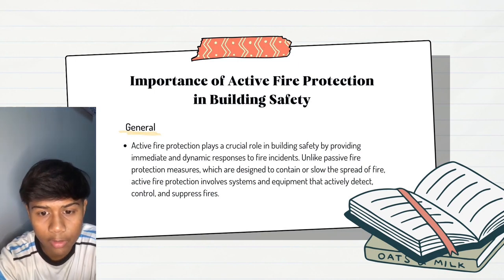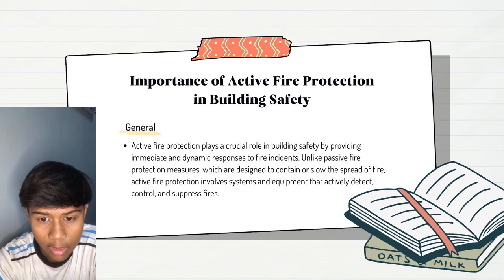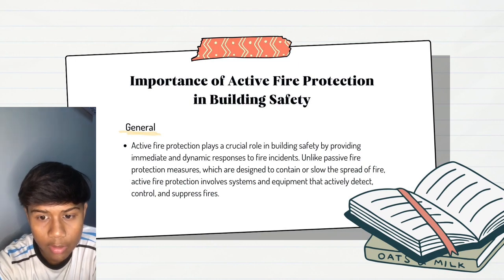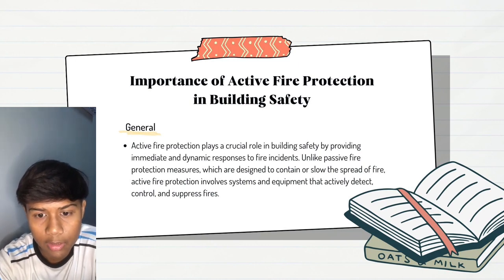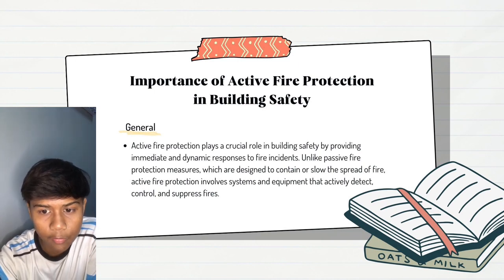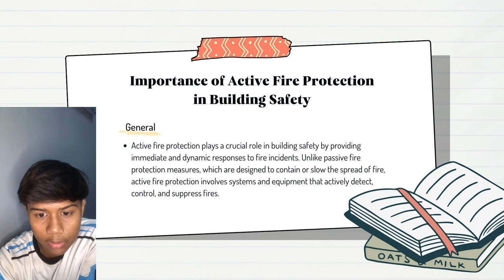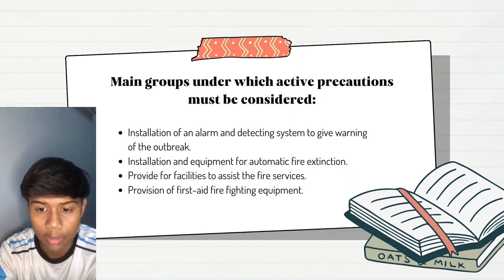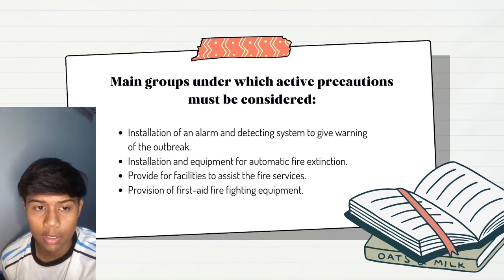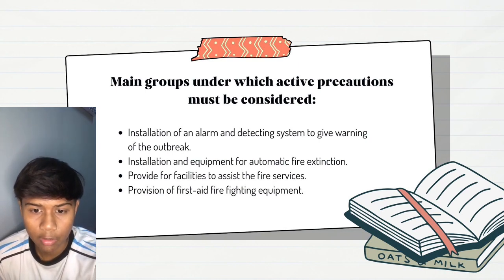Importance of active fire protection in building safety. Active fire protection plays a crucial role in building safety by providing an immediate and dynamic response to a fire incident. Unlike passive fire protection measures, which are designed to contain or slow the spread of fire, active fire protection involves systems and equipment that actively detect, control and suppress fire. Main groups under which active precautions must be considered. First, installation of an alarm and detecting system to give warning of the outbreak.